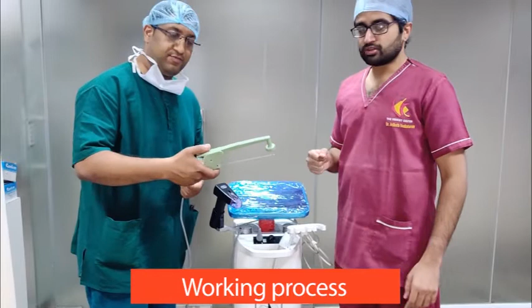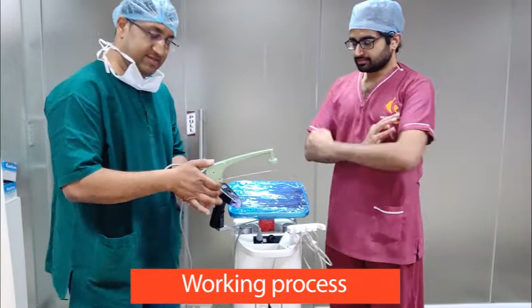Now this cannula is the body tight cannula, which is used to cause the skin tightening. So can you tell us a little bit about how this works? Yes. This is a body tight cannula. We have two types of probe electrode in this, the internal probe and the external probe. The internal probe goes inside the skin at the subdermal layer, and the outer probe is on the skin. The best part is when the upper probe is in contact with the skin and the inner one is working, the heat goes from inner to outside. So we get the dual heating from the skin and from inside.